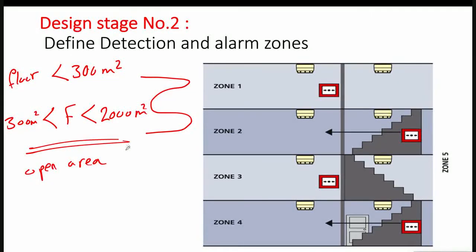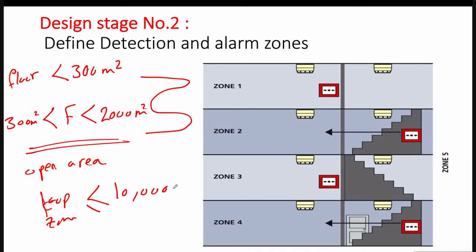For open areas which have no ceiling, like an open garage, one loop or zone can cover up to 10,000 square meters. So it is recommended to assign a complete zone for each floor.